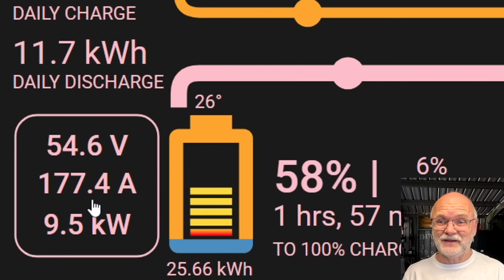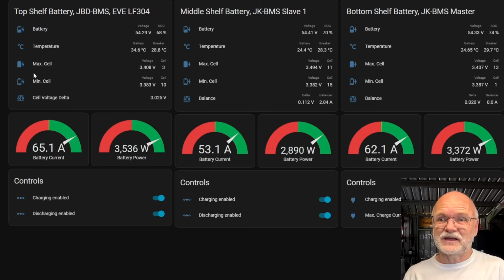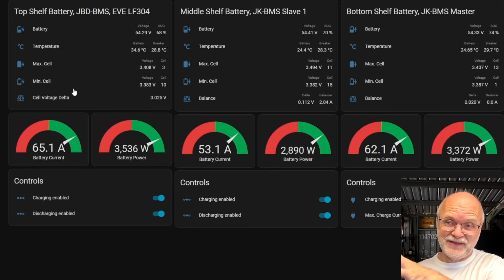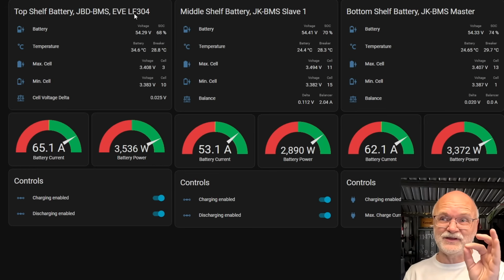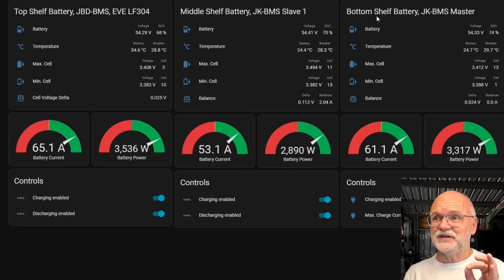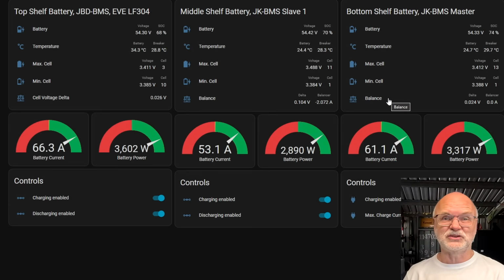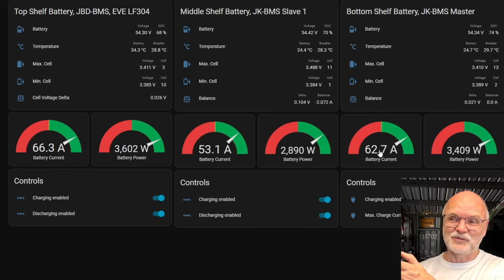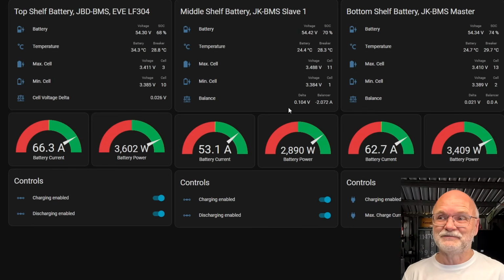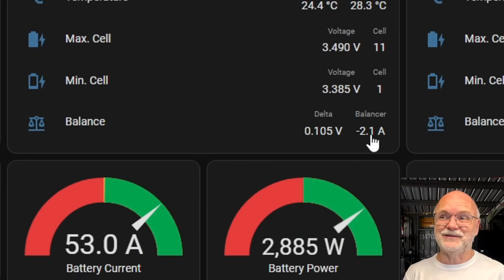Charging the battery again with around 180 amps. Looking at this card, 65 amps are going into the top shelf battery, which is a higher capacity battery than the others — 304 ampere hours, the LF304. These ones here are 280 ampere hour batteries, so the current is naturally a bit lower anyway. But the middle shelf is only 53 amps, and the bottom shelf, which is furthest from the charger, is 61 amps. That makes no sense — this one should be between this one and this one, and should definitely be higher than this one since the bottom is further from the charger, but it isn't. 104 millivolt deviation, and you can see the balancer is already on.